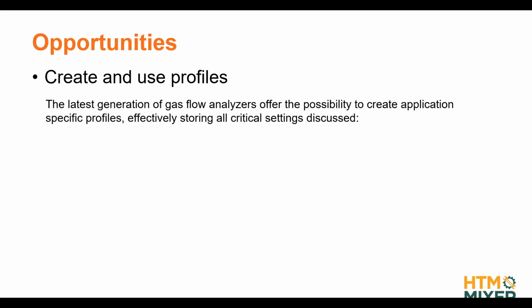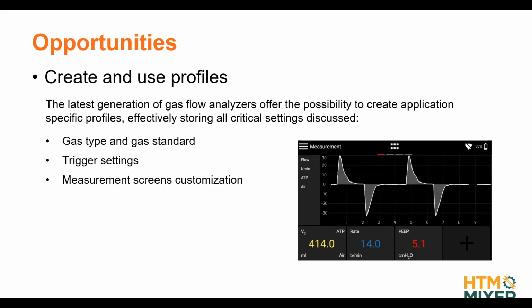Because most modern gas flow analyzers allow you to save all your settings. Let's say you have a specific ventilator, and you talk to the ventilator manufacturer and go through training. You know, okay, this ventilator is using that gas standard, I have these gas types, these are the values and units I need to configure on my screens. Then you can save all that into a profile, and next time when you have the same application, you can just load that profile, and all your settings and customizations of your screen are up to date and correct, right? So this really helps minimize the risk of setup errors and setting errors on your gas flow analyzer.